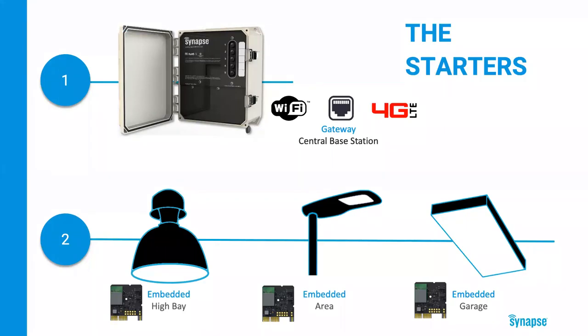Let's take a moment for a quick review of the Simply Snap lighting control system. The first place to start is the gateway or site controller. The central base station is our gateway for indoor and outdoor applications — think of it as the brains of the operation. It talks to all the lights and sensors, provides the user interface, and has a five-button switch built into the front for manual control. One gateway typically manages about 500 lights, and it can be managed locally or remotely over built-in Wi-Fi, Ethernet, or cellular connections. Setup requires just a device with a browser — no server to install, no app to download. It works on any device: smartphone, tablet, laptop, or desktop.